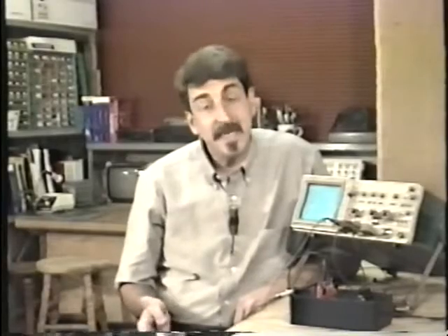Well, I happen to know that it is, in fact, 16.66 milliseconds. I know that because that's the period of our standard 60 cycle or 60 hertz AC power. It's a number that you're going to come up against again and again when you're troubleshooting, so it's a number you'll learn to recognize. Here we have just over 3 divisions, and it looks like about 16 and a half. Remember that oscilloscopes are not particularly accurate when it comes to measuring not only voltage, as I mentioned earlier, but also the period. You end up saying, like I just did, it's about 3 divisions, a little bit more, like 16 and a half, 16 and 3/4, somewhere in that range. And that's really as close as you ever have to get for our applications.